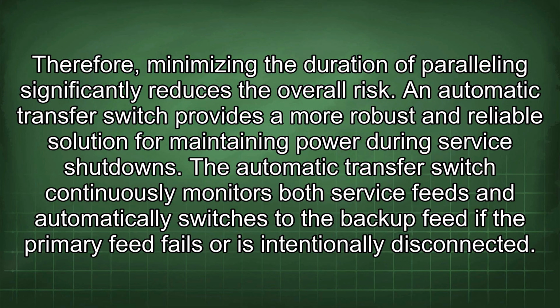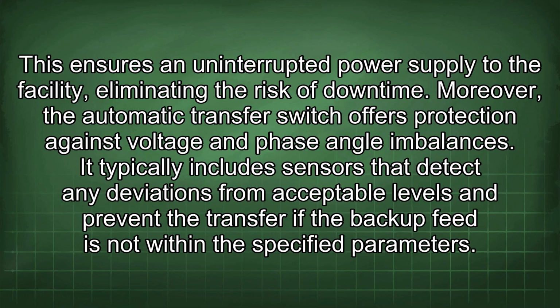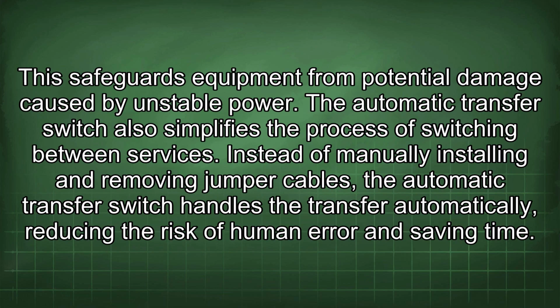An automatic transfer switch provides a more robust and reliable solution for maintaining power during service shutdowns. The automatic transfer switch continuously monitors both service feeds and automatically switches to the backup feed if the primary feed fails or is intentionally disconnected. This ensures an uninterrupted power supply to the facility, eliminating the risk of downtime. Moreover, the automatic transfer switch offers protection against voltage and phase angle imbalances. It typically includes sensors that detect any deviations from acceptable levels and prevent the transfer if the backup feed is not within the specified parameters. This safeguards equipment from potential damage caused by unstable power.